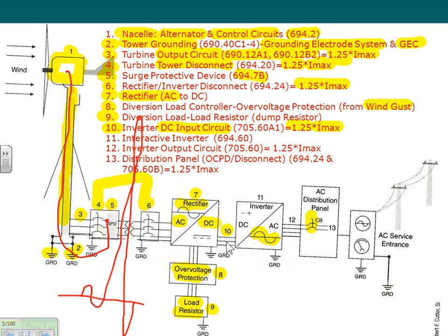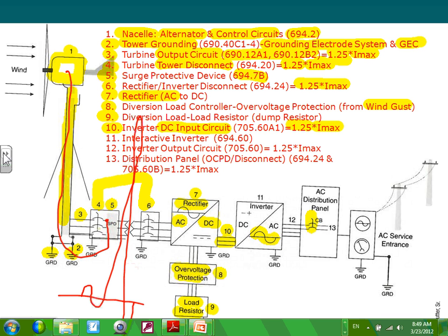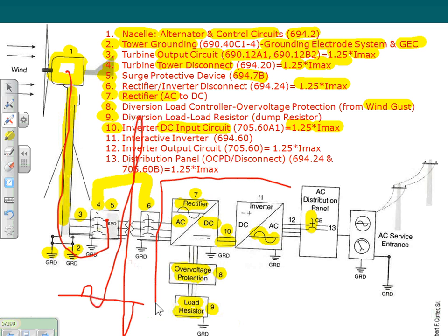And these conductors right here, now these are DC, right in this area, number 10. So most likely you're going to have a positive, negative, and equipment ground conductor, 3 conductors. If it's a bipolar, they're going to have 4 conductors: 2 positive and a negative plus the equipment ground conductor. So, any comments, guys, about this? Usually the converter, inverter, the whole package is in one location together with the source, with the dump load. So usually these are associated with each other. They're going to be in one area, might be even in one package, inverter, converter.